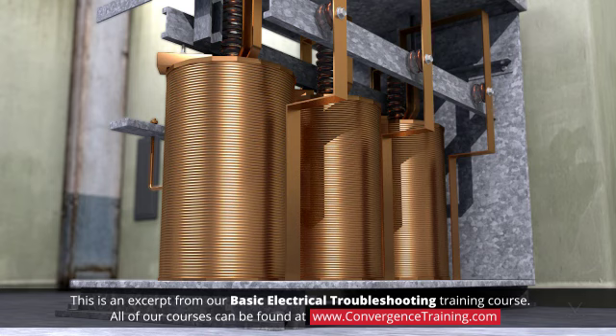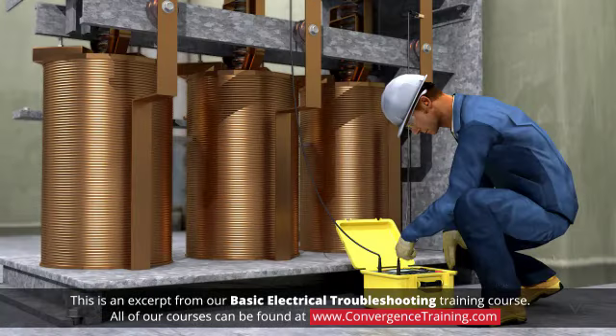Isolating a power transformer is a little more difficult than isolating a motor, but once it is offline, continuity and resistance tests can be run on the phases as described for testing motor windings.